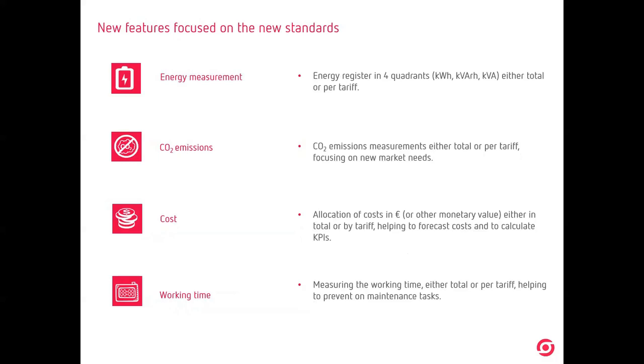Our analyzers are measuring the energy, obviously, in four quadrants, consumption and generation: active, reactive, apparent, in total, in absolute, or by tariff, divided in different periods of time, okay. We are measuring, on the display and by communication, CO2 emissions. We are measuring also the energy costs. So now we can see the cost directly on the display of the analyzer. We can see the euros, dollars, whatever, directly on the analyzer or by communications. And we are also showing the working time.